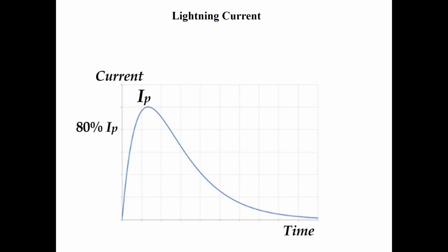Now we go to a little bit of lightning characteristics. I'm not going into details because this is not about lightning, it's about lightning protection. What you see is a very typical lightning current waveform. This is somewhat like a double exponential waveform, but more complex. Usually we represent the lightning current by the Heidler waveform, which is what you see here.